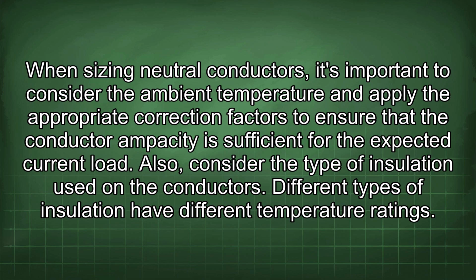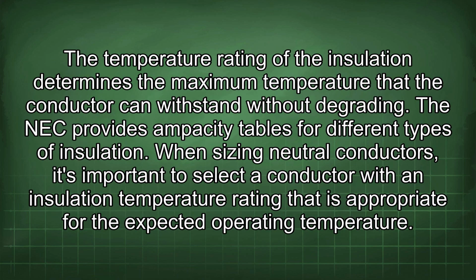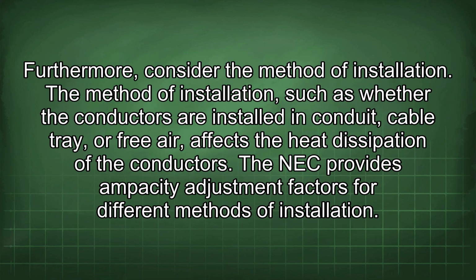Also, consider the type of insulation used on the conductors. Different types of insulation have different temperature ratings. The temperature rating of the insulation determines the maximum temperature that the conductor can withstand without degrading. The NEC provides ampacity tables for different types of insulation. When sizing neutral conductors, it's important to select a conductor with an insulation temperature rating that is appropriate for the expected operating temperature.